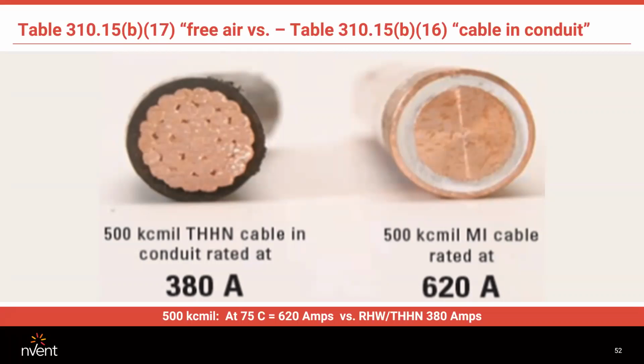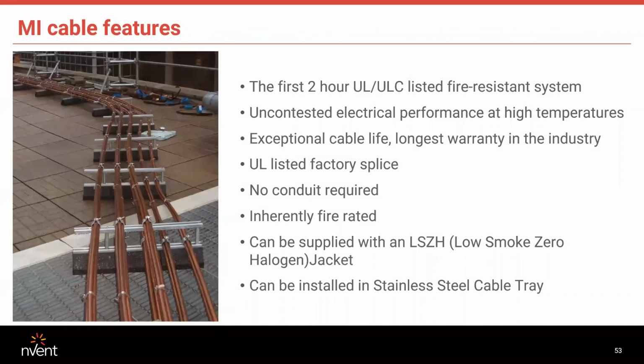So good rule of thumb, 300 feet or less at 480 volts, you're going to be good. 125 feet or less at 208, you're going to be good. Once you start to exceed those, you want to go to our website and check the voltage drop on our calculator. No conduit needed. Note this installation photo here.